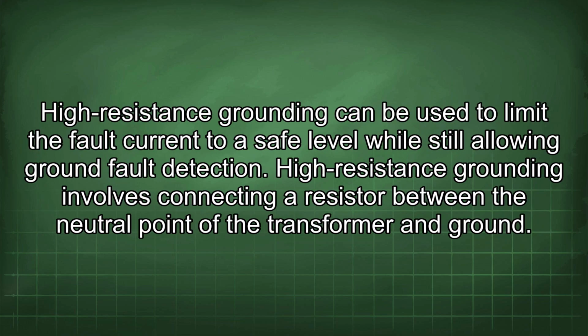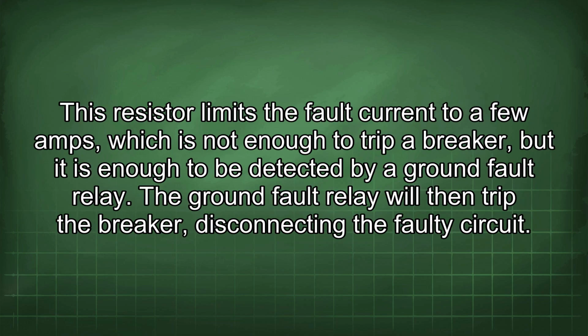High resistance grounding can be used to limit the fault current to a safe level while still allowing ground fault detection. High resistance grounding involves connecting a resistor between the neutral point of the transformer and ground. This resistor limits the fault current to a few amps, which is not enough to trip a breaker, but it is enough to be detected by a ground fault relay. The ground fault relay will then trip the breaker, disconnecting the faulty circuit.